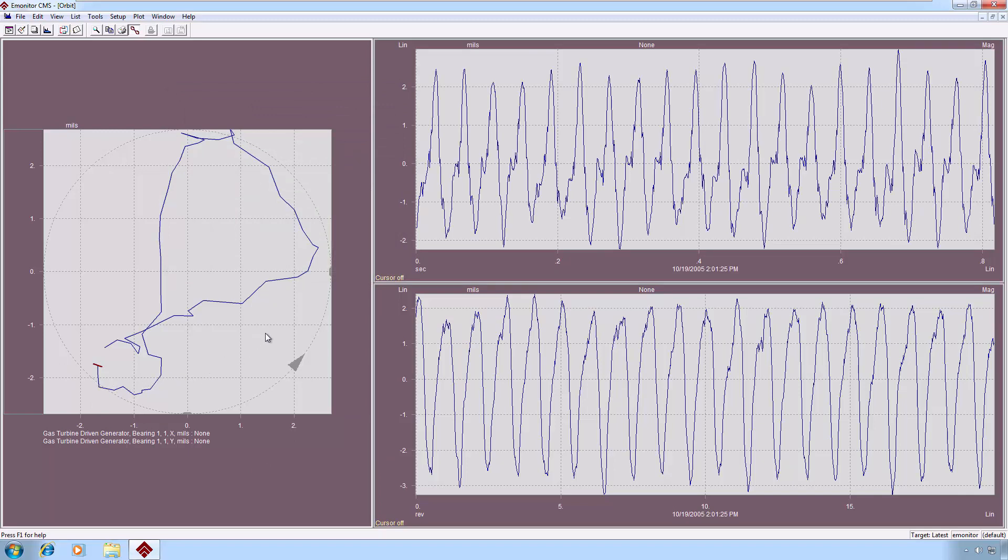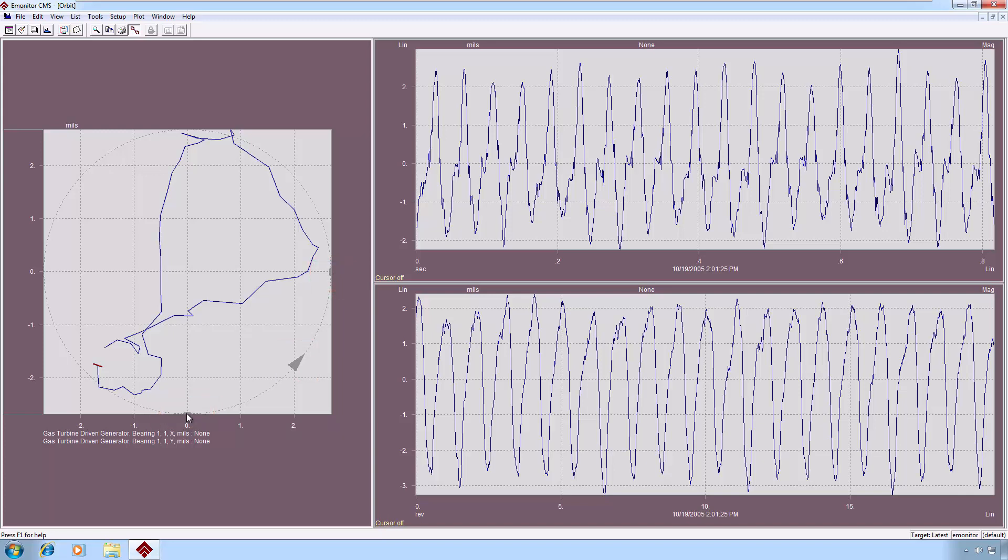This one is giving us sort of the characteristic figure eight shape that is representative of a phase change. The direction of rotation is indicated by the arrow, and there's a little gray pad on the top and bottom which are indicating the specified sensor orientation. And those values are provided in the location pane. And you must fill in those sensor orientation values or you will not get the expected result in the orbit plot.